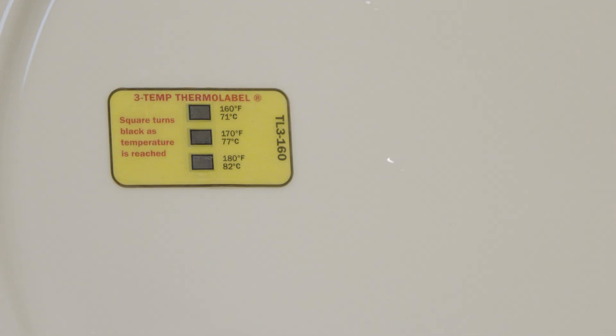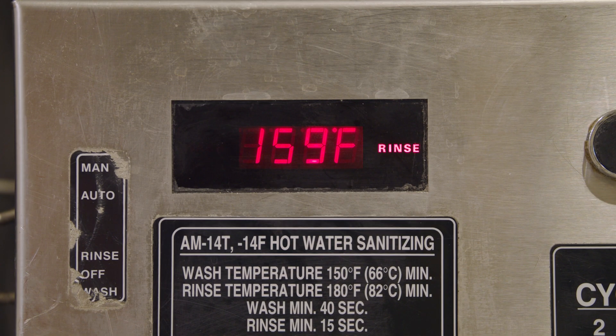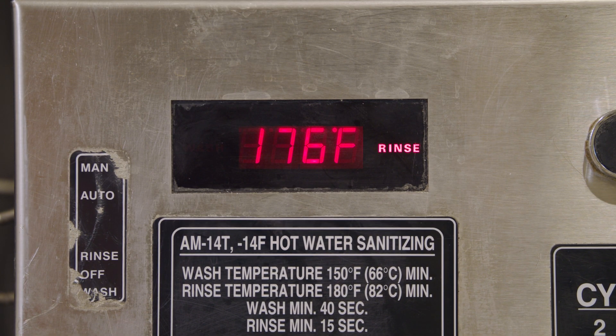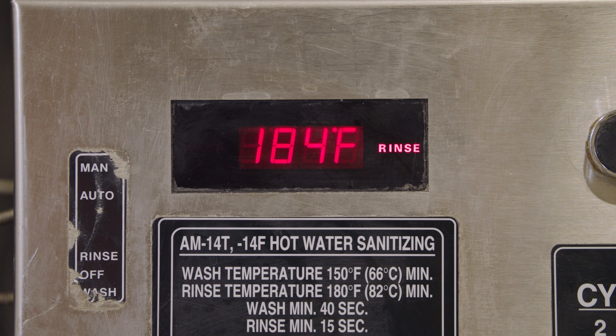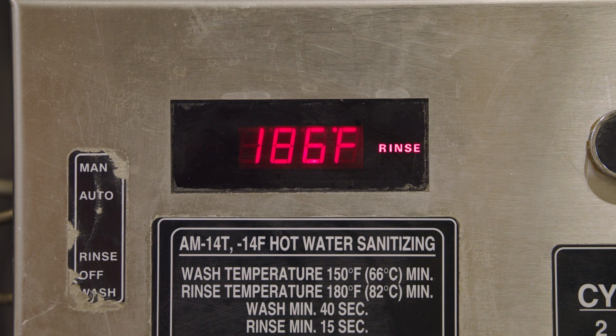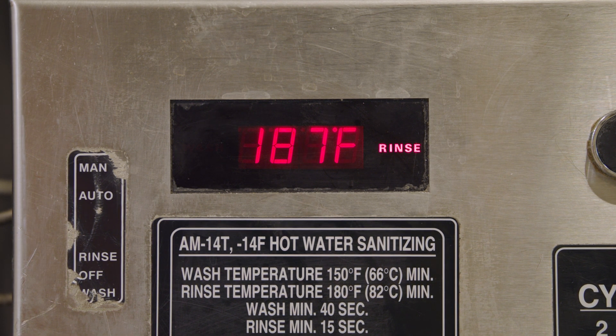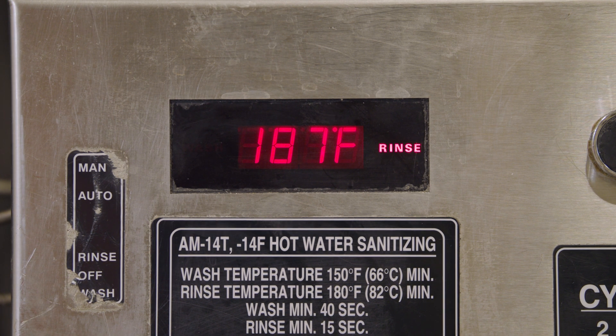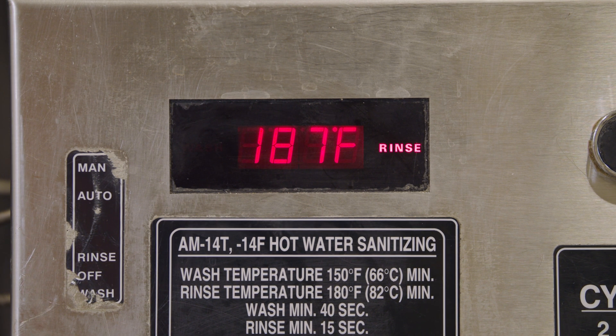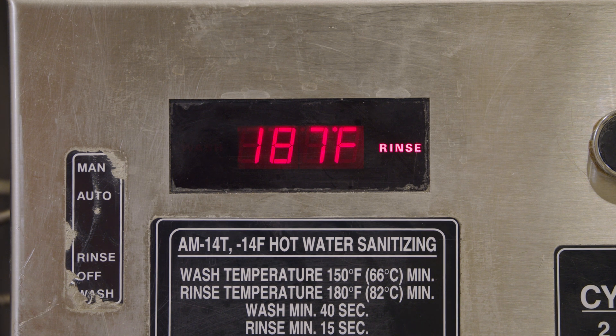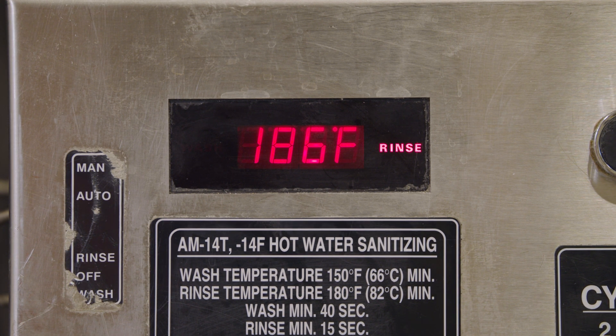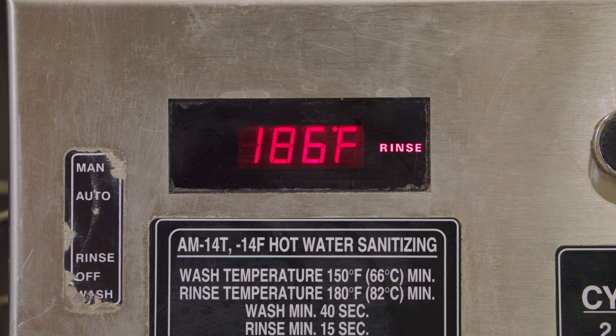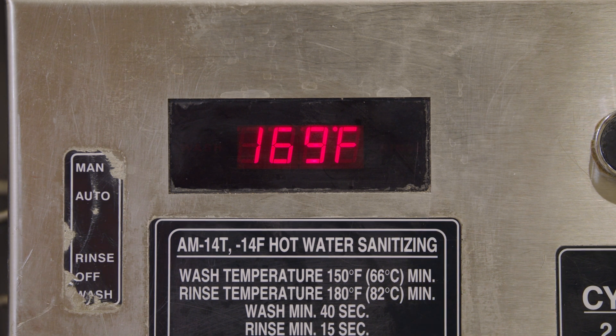If the 170 or 180 degree squares have turned black, the dishwasher has exceeded the required sanitizing temperature by at least 10 or 20 degrees. If the dish were only a few degrees higher than the required temperature, that would be fine, and possibly even desirable as insurance that the dish was sanitized. A full 10 degrees or more is unnecessarily wasteful. If repeated tests find that the dishwasher is consistently exceeding the needed temperature, it may be wise to contact your service person to adjust the temperature and eliminate the unneeded waste of energy.